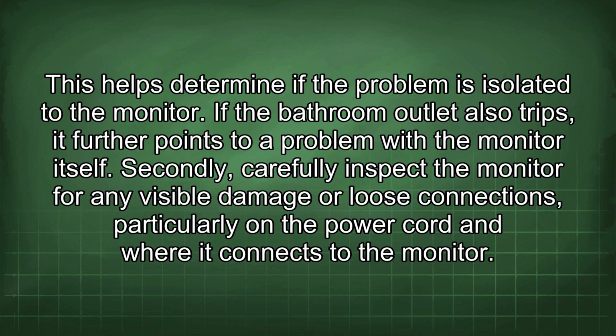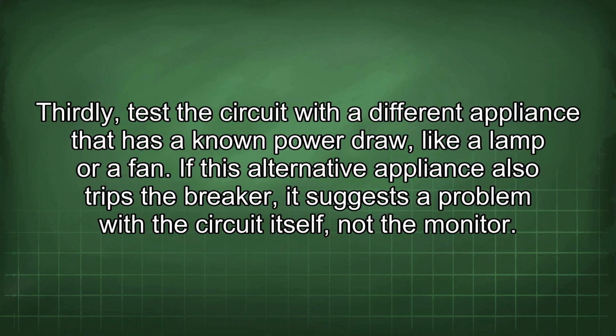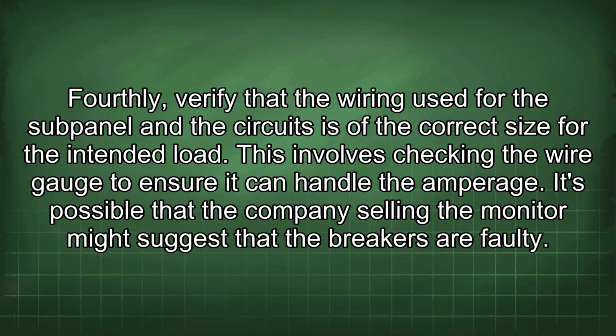connects to the monitor. Thirdly, test the circuit with a different appliance that has a known power draw, like a lamp or a fan. If this alternative appliance also trips the breaker, it suggests a problem with the circuit itself, not the monitor. Fourthly, verify that the wiring used for the subpanel and the circuits is of the correct size for the intended load. This involves checking the wire gauge to ensure it can handle the amperage.